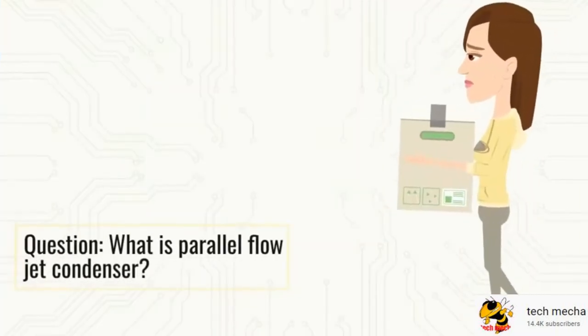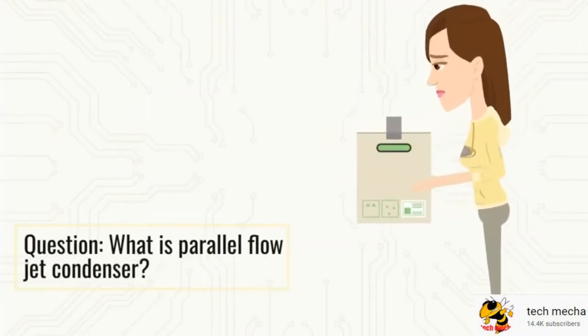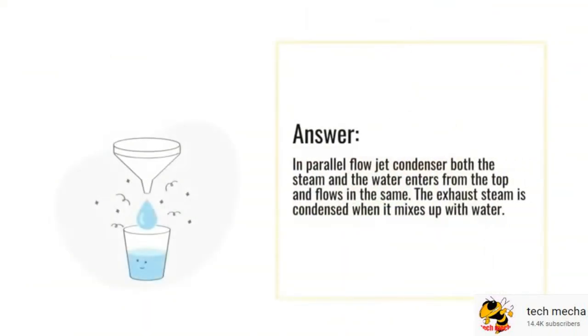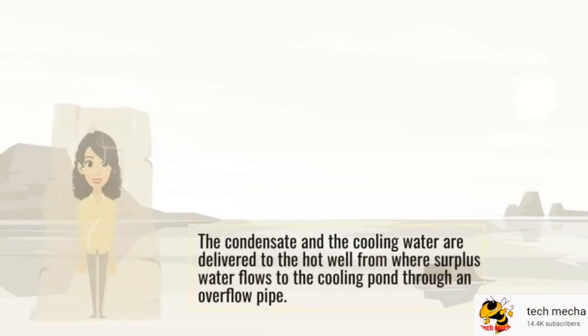What is a parallel flow jet condenser? In a parallel flow jet condenser, both the steam and the water enter from the top and flow in the same direction. The exhaust steam is condensed when it mixes up with water. The condensate and the cooling water are delivered to the hot well, from where surplus water flows to the cooling pond through an overflow pipe.